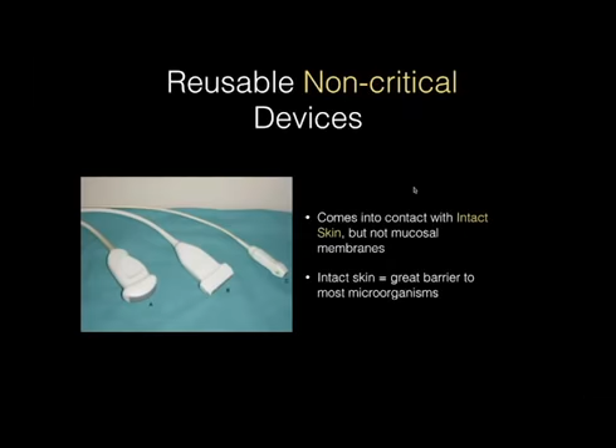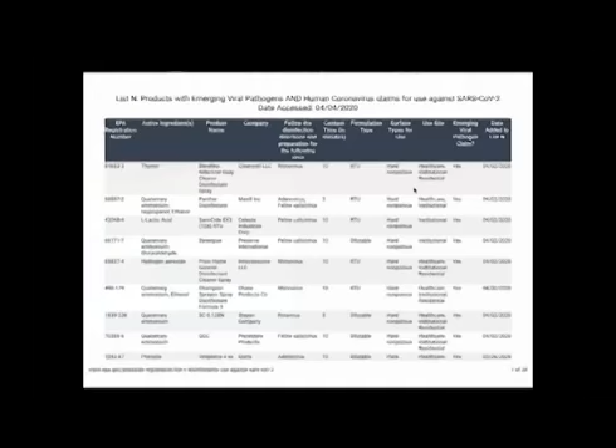For reusable non-critical devices, such as our curvilinear, linear, and phased array transducers that are coming in contact with intact skin, we really believe that basic low-level disinfection is still the way to go, and I'll explain that in a little more detail. Again, this is the list of EPA guidelines for products that could be used for low-level disinfection in the period of SARS-CoV-2.